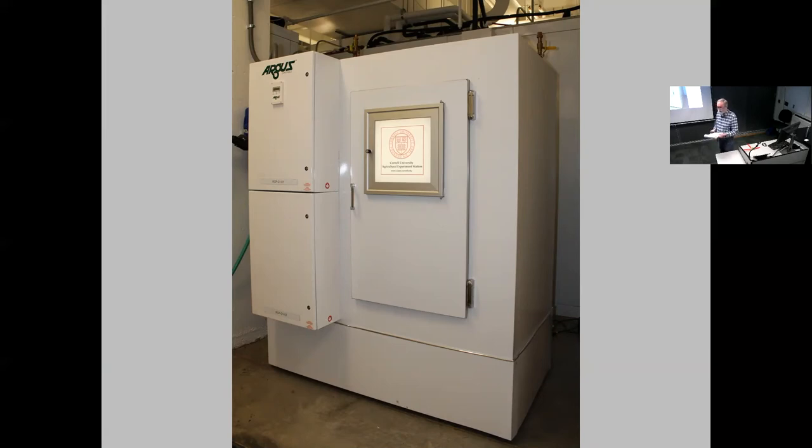All the other parts that we needed were readily available. I can even get some of them overnight and free shipping overnight, too. The main parts are really one pump, two heat exchangers, two valves, two coils, a few fans, and a couple of fluorescent fixtures. The insulated box was set on a pedestal, a sort of metal frame, and that brought the box up to a comfortable working height, but still allowed it to pass underneath doorways. So wherever we intend this chamber to go, we sort of have to walk that route and measure, will it fit in elevators? Can it fit through doors? These pedestals also have wheels on them and leveling feet, so we can just roll it to wherever we need it to go.